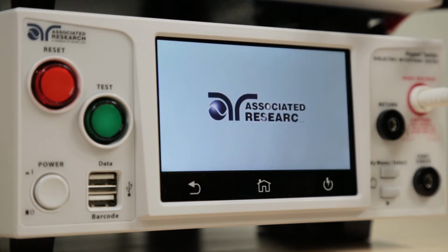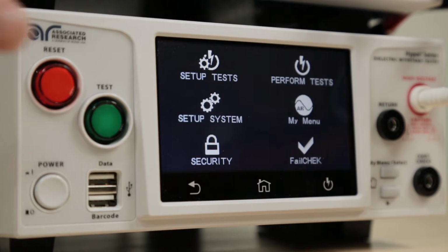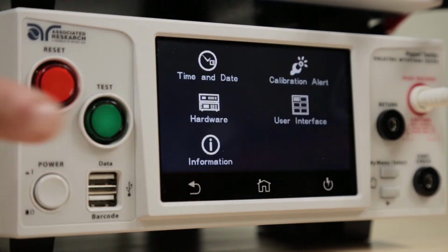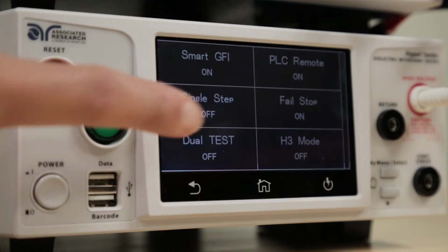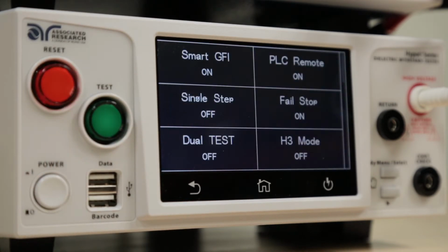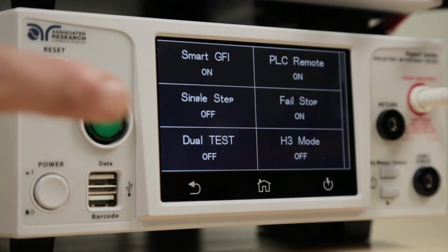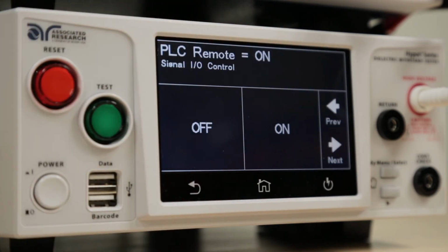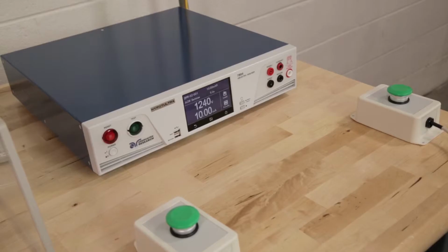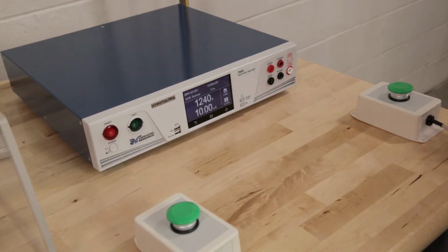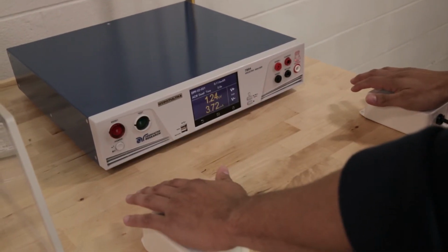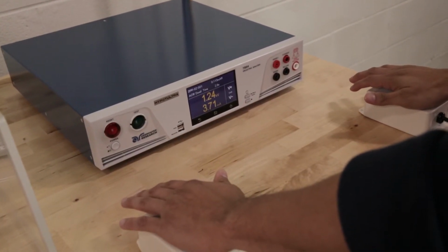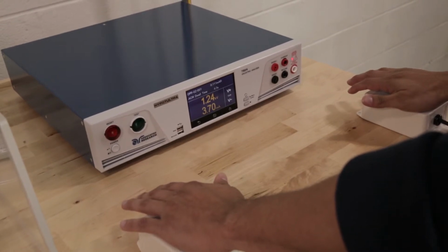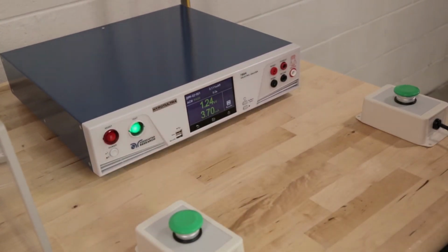First, we will turn on the dual test function. Select Setup System. Next, we will turn on the PLC remote setting. Select Hardware, PLC Remote. Set PLC Remote to On. Now you can select the Perform Test button and load your test file. Use the DPR-02 to initiate a test. Releasing pressure from the DPR buttons will result in an aborted test.